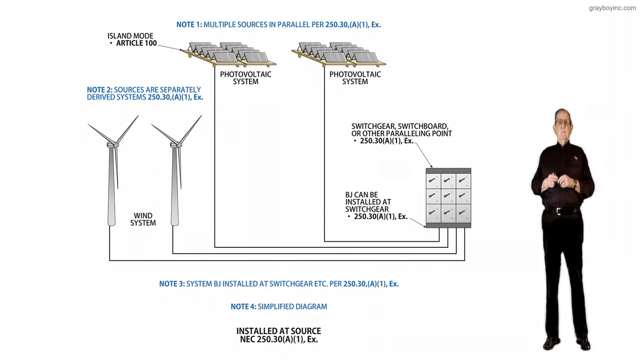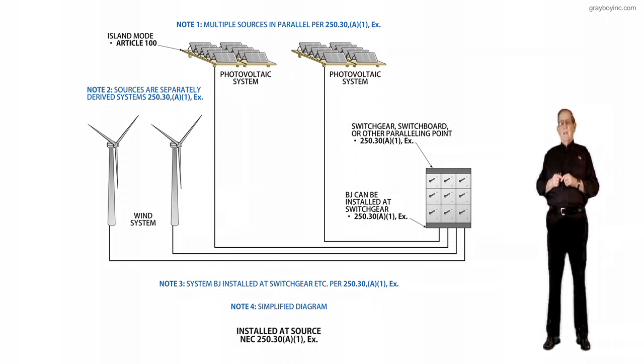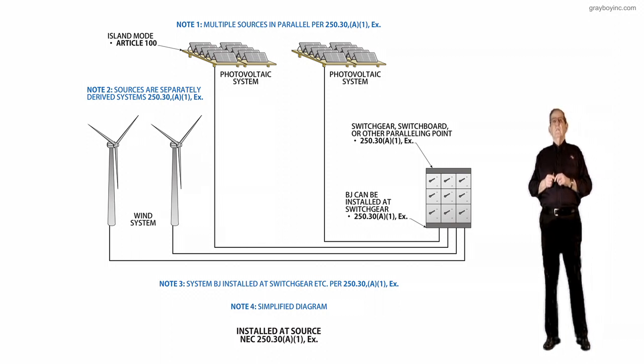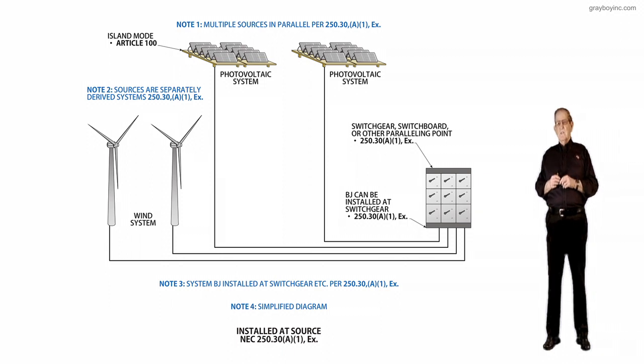And then when you look at note two, sources are separately derived systems in accordance with 250.30A1 exception. And then notice if you had, say, an island mode for those PV systems, you'd see Article 100, and it explains what an island mode is where we were having some problems in the past determining exactly what that was.